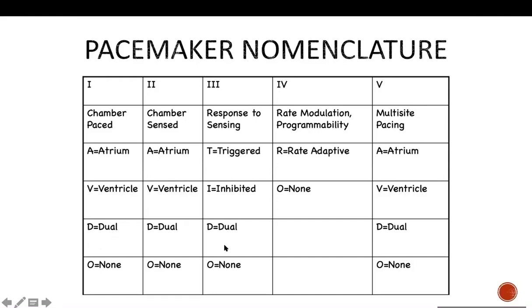Did you understand how DDD works? Yes. You could either pace the atrium or ventricle in response to the sensing of the atrium or the ventricle, and you could either inhibit pacing if you sensed, or trigger pacing if you sense the other chamber. So in DDD mode, it's always interactive, depending on what's happening. You could inhibit one and trigger the other. For example, you could inhibit pacing the atria because you have an underlying atrial rhythm, but you trigger ventricular pacing because there is no ventricular signal. So you used both: you inhibited pacing in the atrium, but triggered pacing in the ventricle. That's why DDD is interactive.